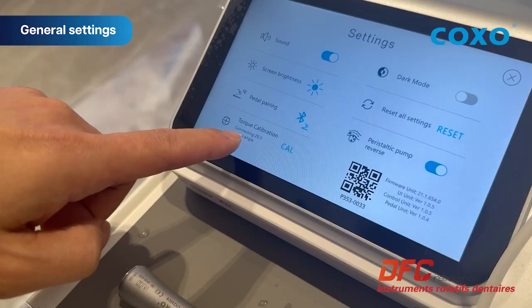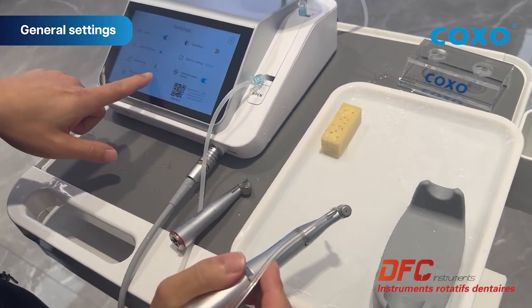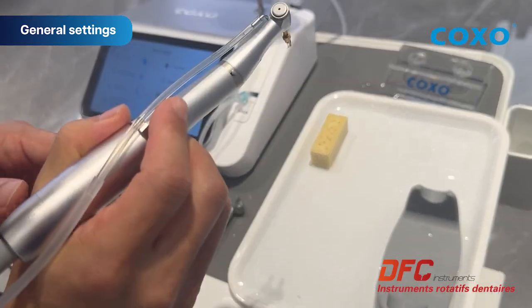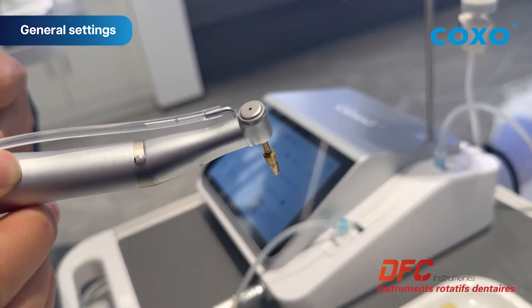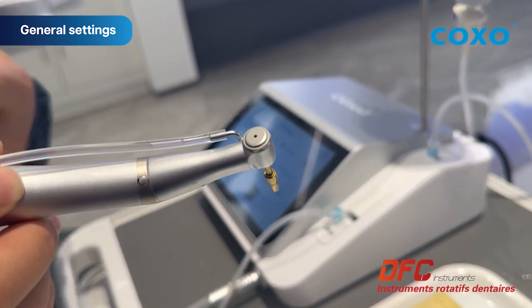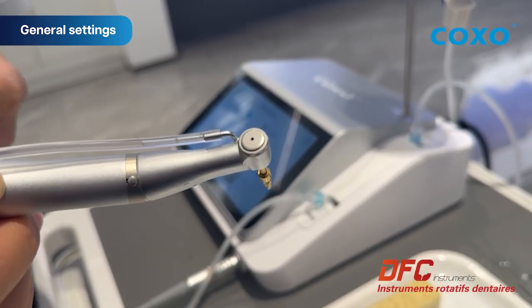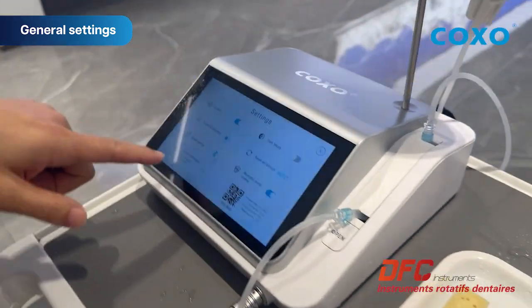Finally, for implantology contra angles, you can use the torque calibration procedure here. Press Cal to start the procedure. The contra angle starts up to its maximum speed. It is highly recommended to perform this procedure every time you change the implantology contra angle. When OK appears, then the calibration is effective.